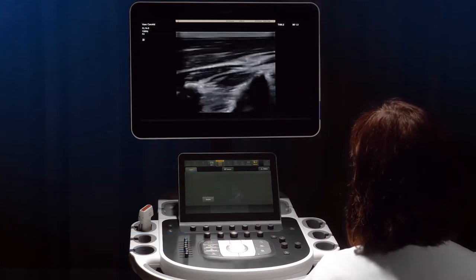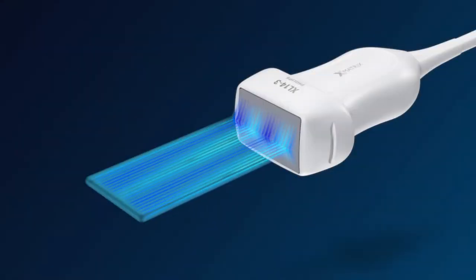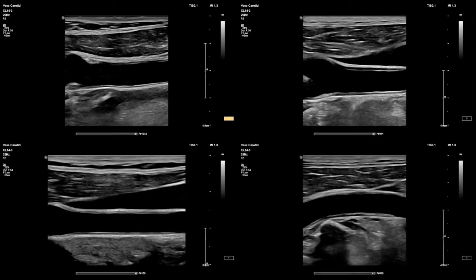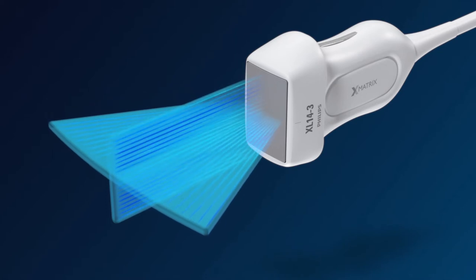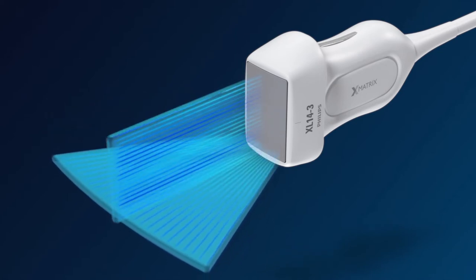Let's know about types of transducers used in ultrasound machines for different applications. Let's begin with straight linear array probes. The straight linear array probe is designed for superficial imaging. The crystals are aligned in a linear fashion within a flat head and produce sound waves in a straight line. The image produced is rectangular in shape. The probe has higher frequencies, 5 to 13 megahertz, which provides better resolution and less penetration. Therefore, this probe is ideal for imaging superficial structures and in ultrasound-guided procedures.